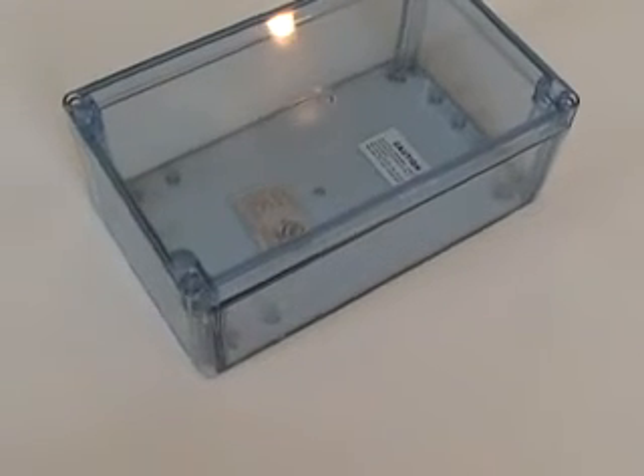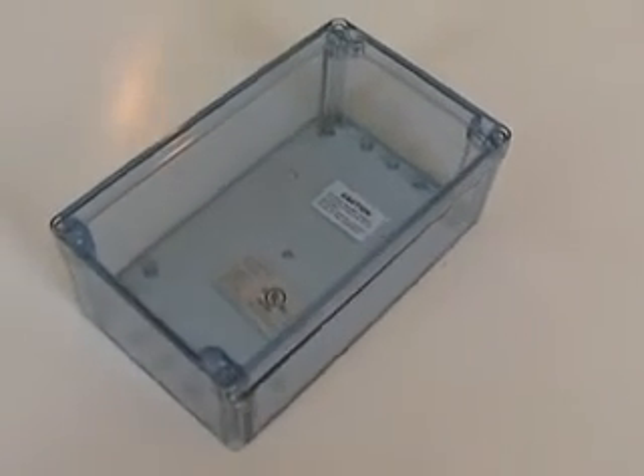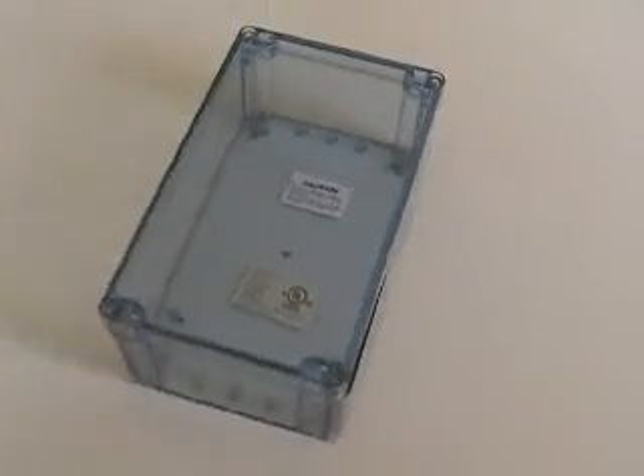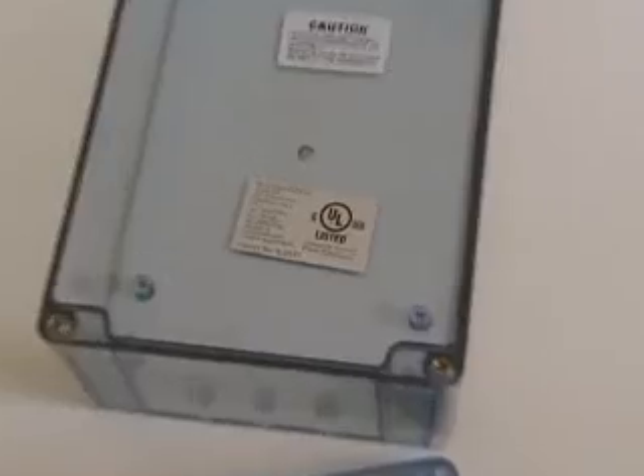The BT Series is manufactured out of transparent blue polycarbonate material, designed to reduce the need to remove the cover. It has a silicone gasket to ensure the NEMA 4X rating and is designed to IEC529 IP65 specification. It is UV stabilized with a UL94HB flammability rating.